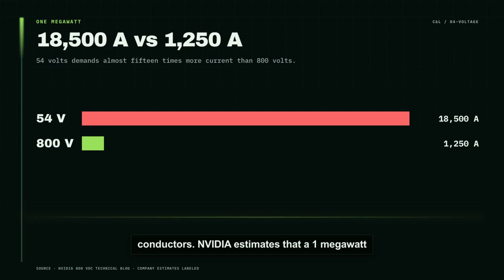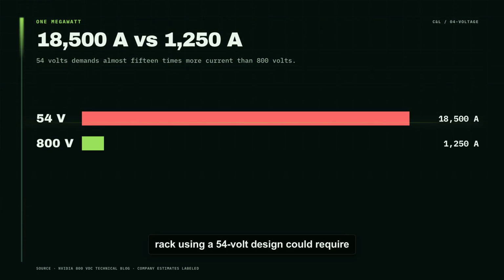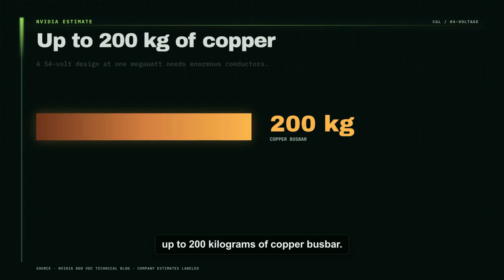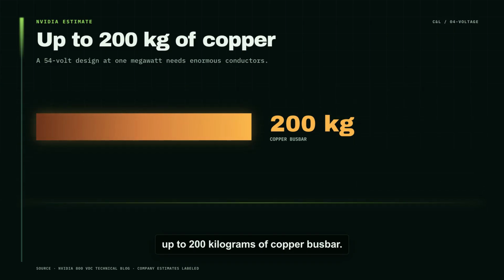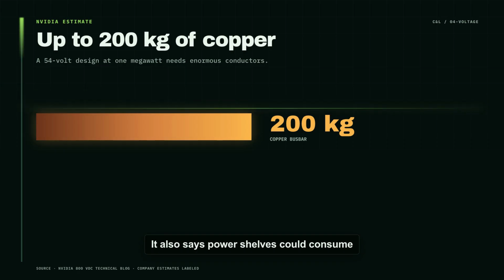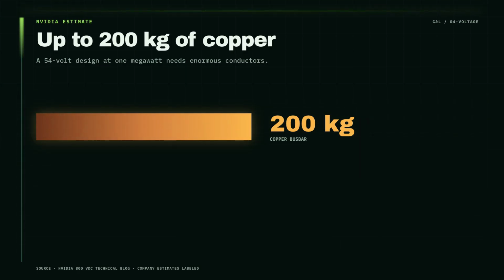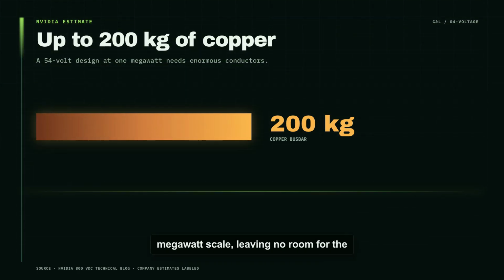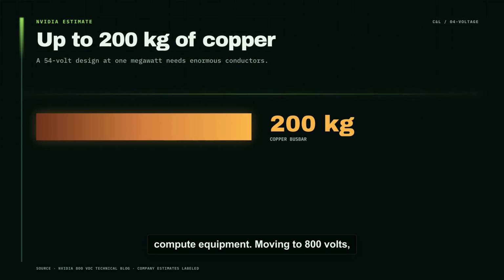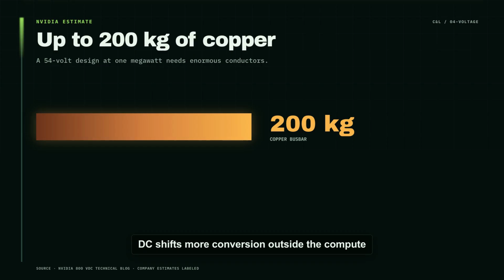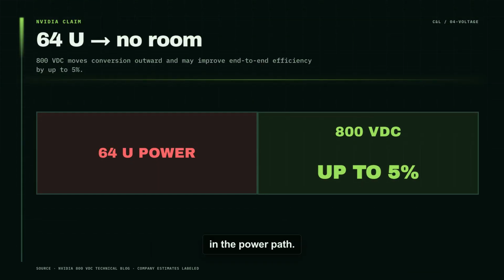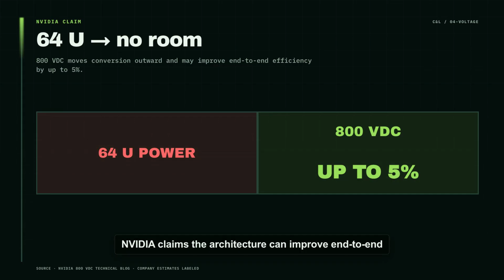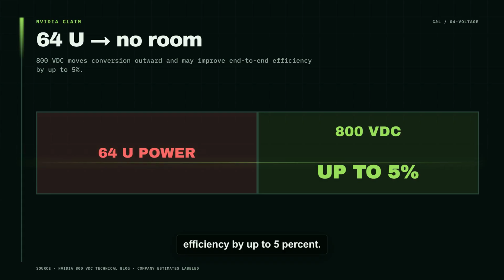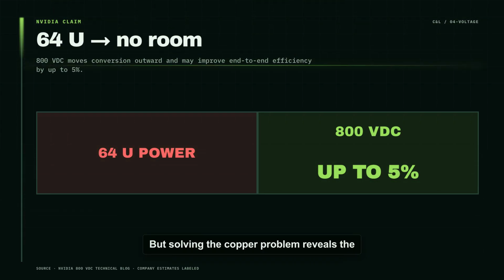NVIDIA estimates that a 1 megawatt rack using a 54-volt design could require up to 200 kilograms of copper busbar. It also says power shelves could consume as much as 64 rack units at megawatt scale, leaving no room for the compute equipment. Moving to 800 volts DC shifts more conversion outside the compute rack and reduces the number of steps in the power path. NVIDIA claims the architecture can improve end-to-end efficiency by up to 5%. But solving the copper problem reveals the next one.